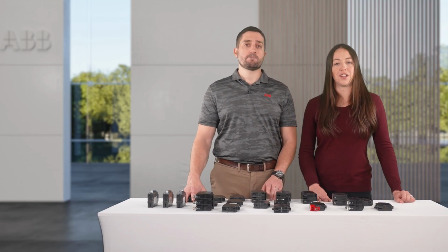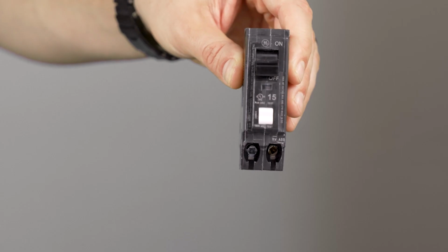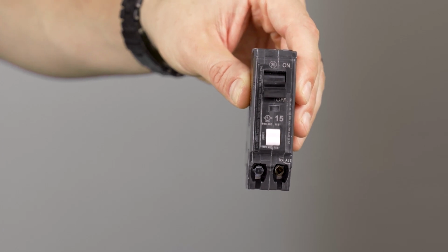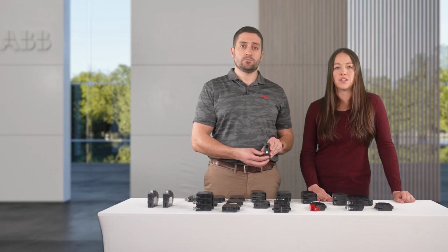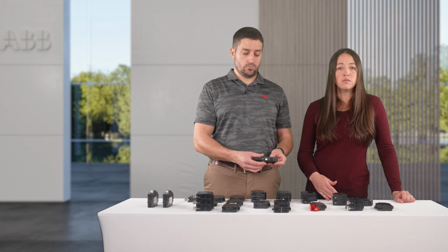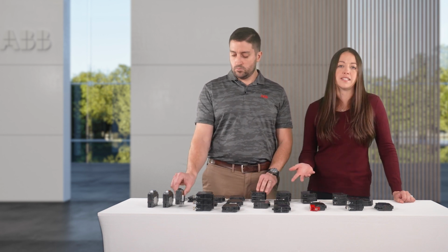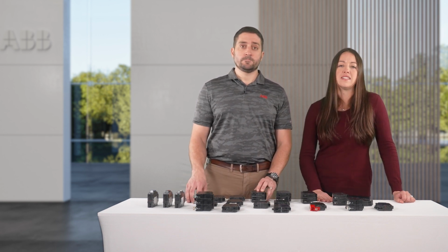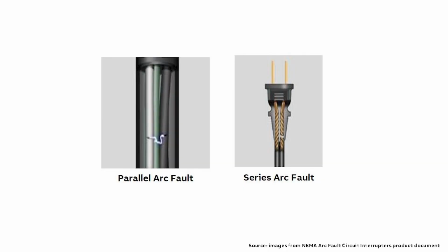Another great option for protection is an arc fault circuit interrupter, which detects arc faults and then de-energizes the breaker. Combination arc fault circuit interrupters protect against overloads, short circuits, parallel arcs, and series arcs. A parallel arc is the unintentional flow of electricity between 2 separate wires, whereas a series arc fault occurs when the unintentional flow of electricity is over a gap within a single wire.